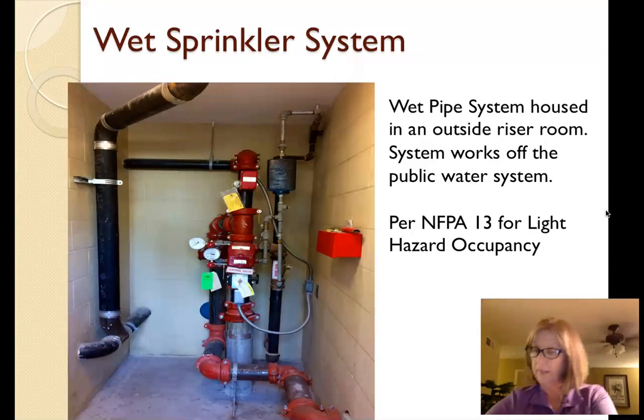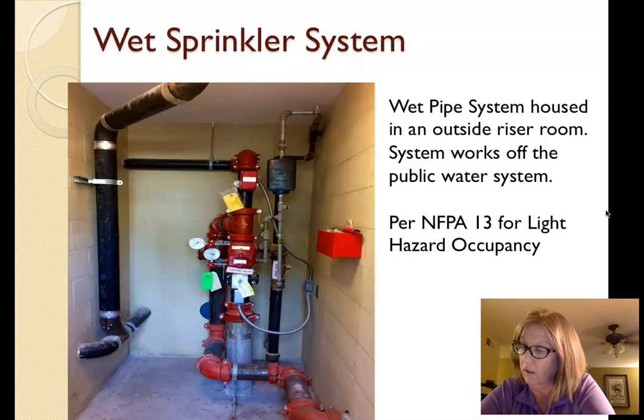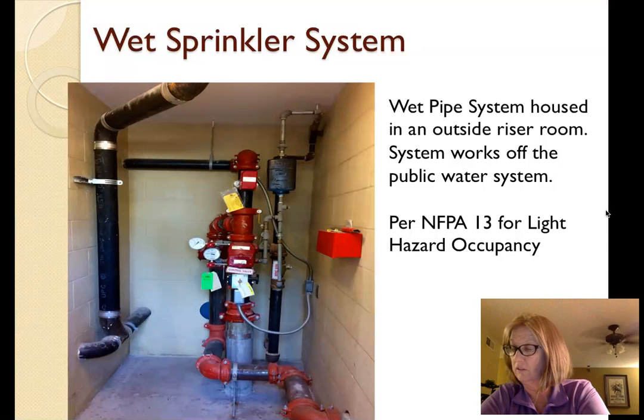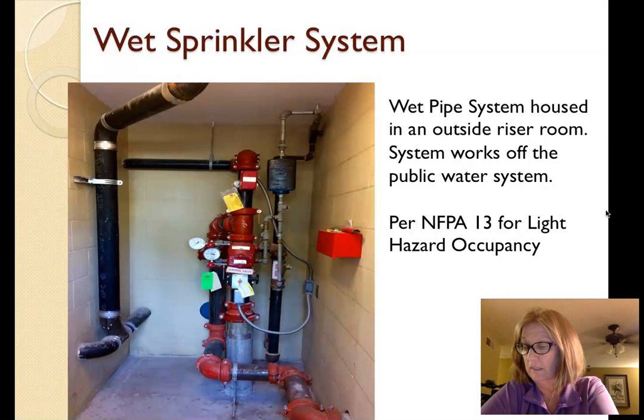Because this is a wet sprinkler system, the room must be climate controlled and maintained at 40 degrees Fahrenheit at all times. The riser room was last inspected in November of 2015 by Industrial Commercial Fire Protection, which means the sprinkler system is now due to be inspected this month. The inspection tags are all kept in the room from year to year, and the main tag that showed pressures was attached to the system.